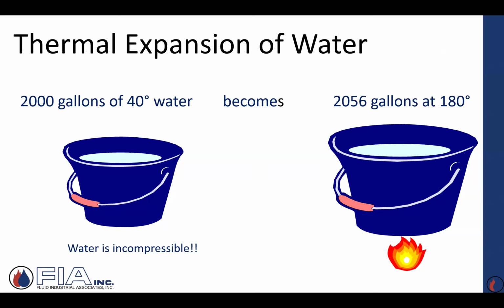2,000 gallons of water, fill the system at 40 degrees street temperature, say. I heat the water to 180 and I have an additional 56 gallons of volumetric expansion. Water's not compressible. Where do I put this 56 gallons? And don't create either one, a bomb, or two, a relief valve that exceeds that expansion and opens up to protect the equipment and dumps all the water on the floor. That's why we have expansion tanks, diaphragm, bladder, whatever, to accept that expanded volume, let the pressure rise, but never get to the point where it's critical. It's below that threshold. So, like I said, picture speaks 1,000 words. This is the reason for expansion tanks, or one of the big reasons.